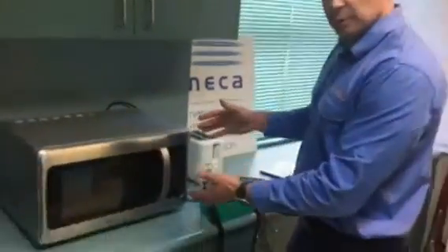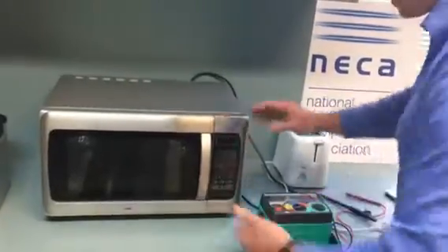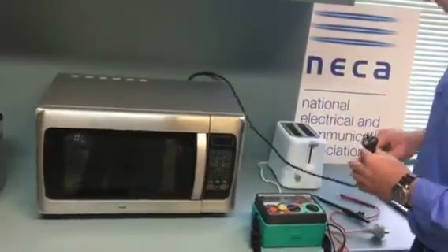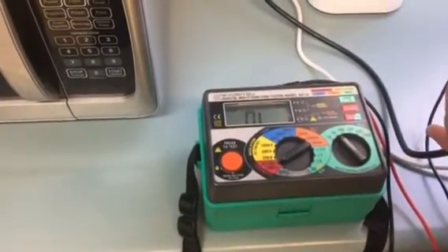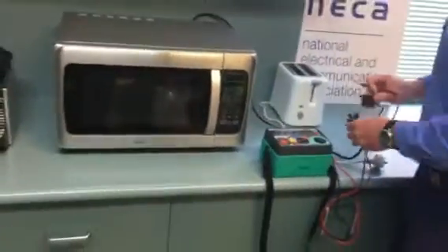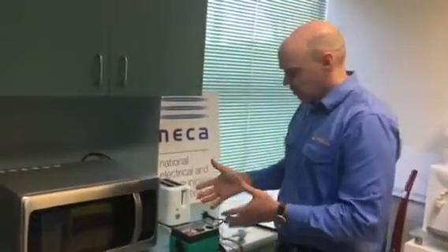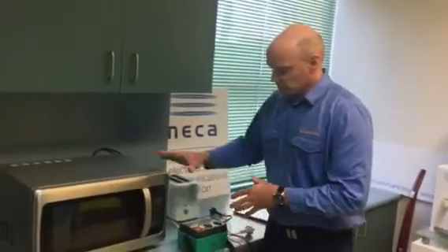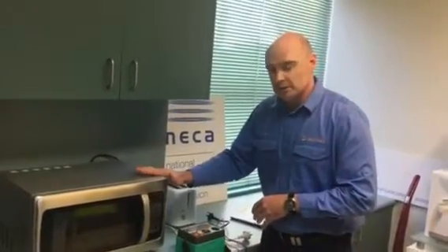But have a look at this appliance here, a microwave oven. There's no physical switch like the toaster on here. If I test quickly between the active and neutral pins, you'll see that's an open circuit, and I don't have any way of closing that circuit. So that to me is indicating that I can't really use this instrument on the insulation resistance test to test this adequately under 3760. I'd need to perform a leakage current test.